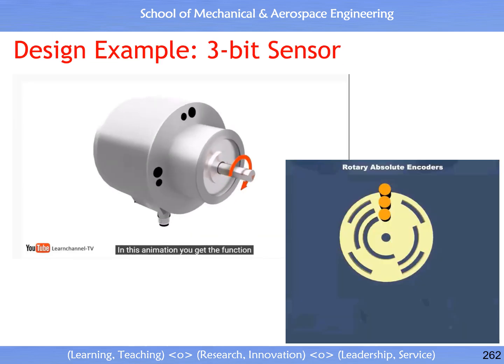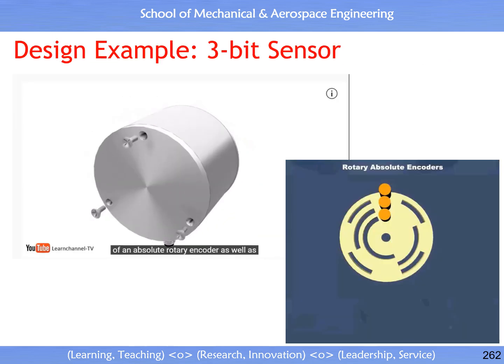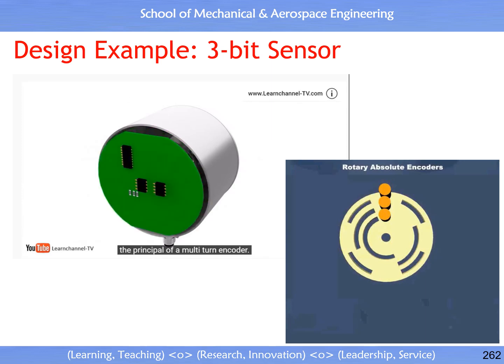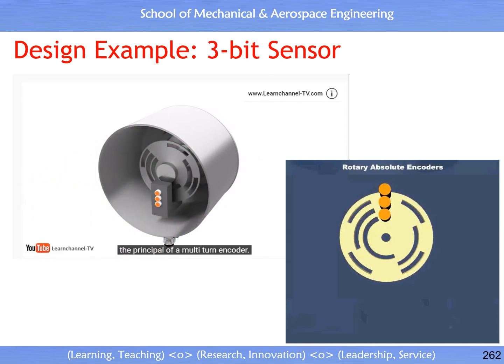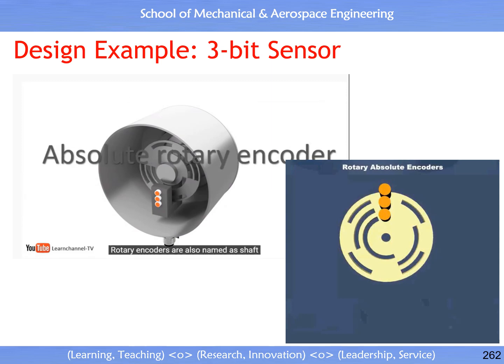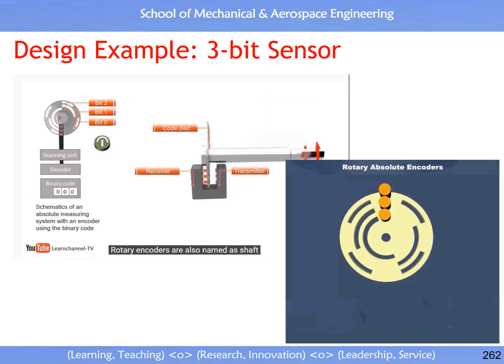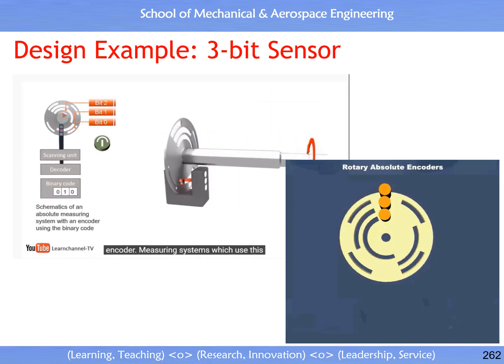In this animation, you see the function of an absolute rotary encoder, as well as the principle of a multi-turn encoder. Rotary encoders are also called shaft encoders. Measuring systems which use this type of encoder can be classified as indirect and digital. The absolute encoder has a coded disk. As an example, you see here the binary code.